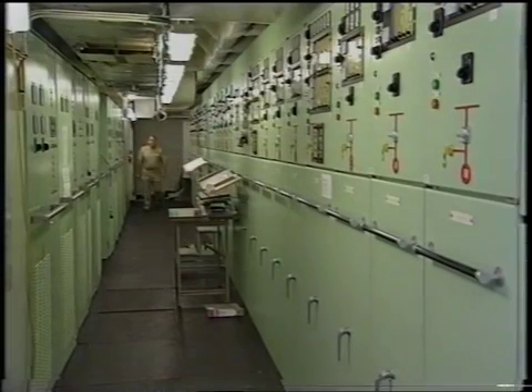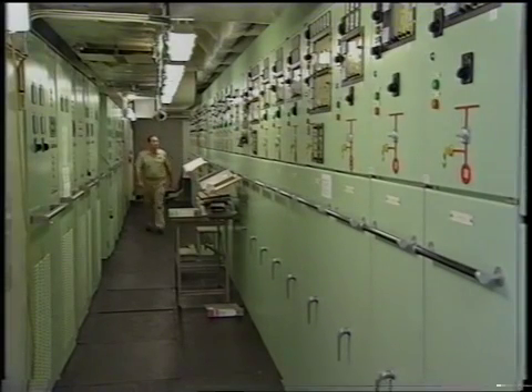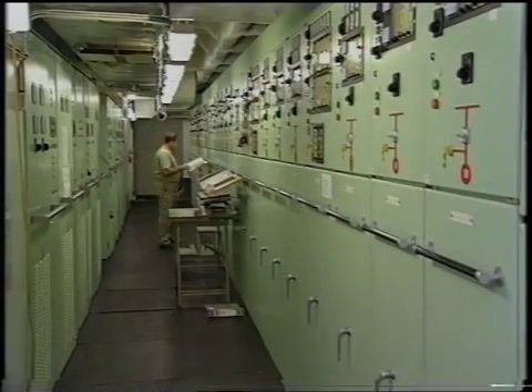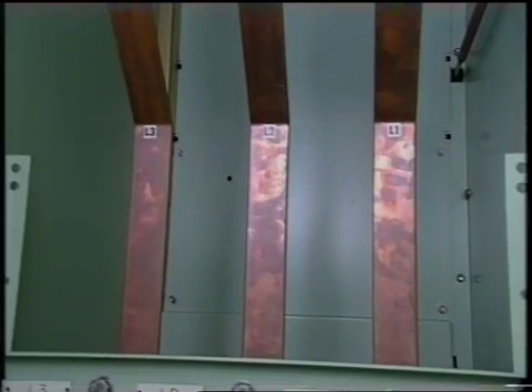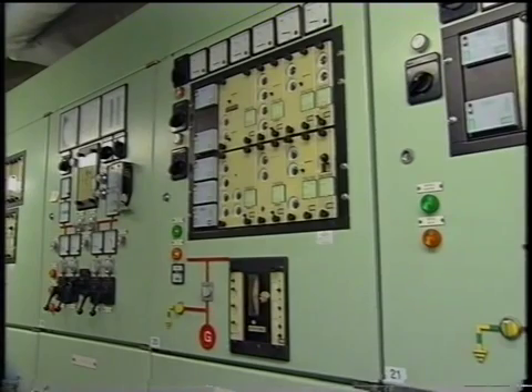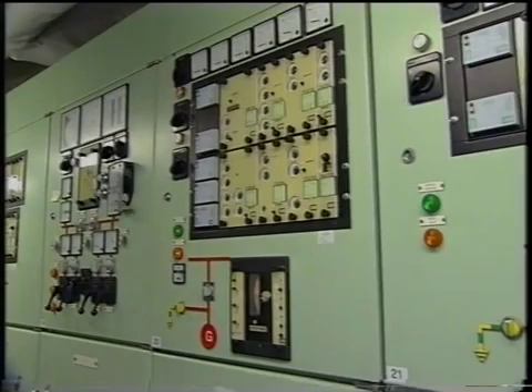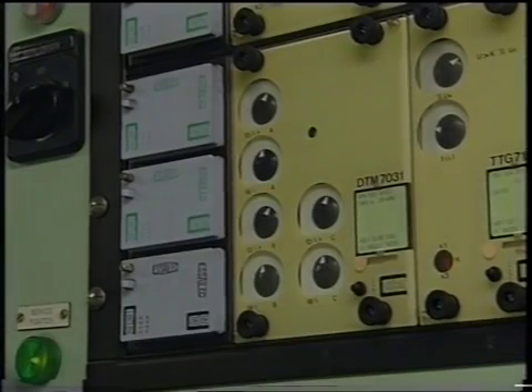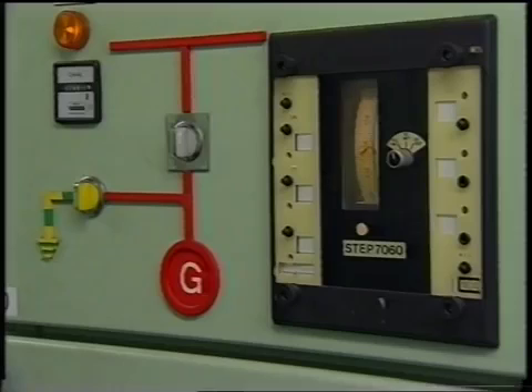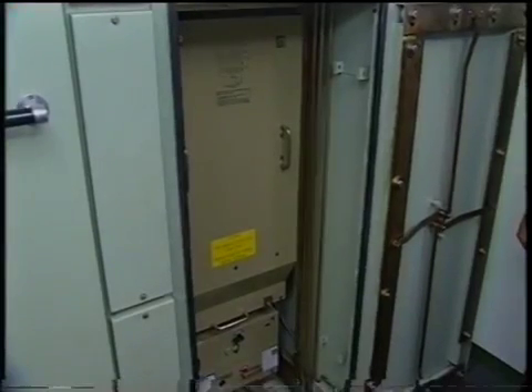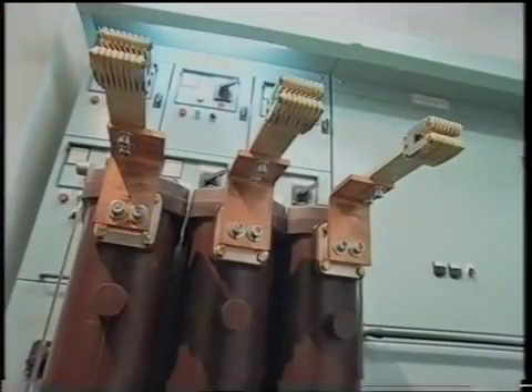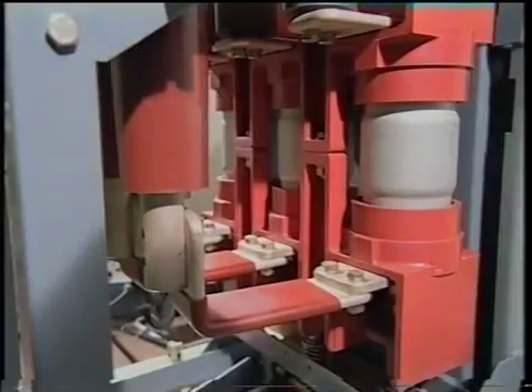The main 6.6 kV switchboard will be separate from the engine control room. Here are the 6.6 kV bus bars and the main protection relays. These protection relays continuously monitor critical operation levels such as currents, voltages, earth leakage, unbalanced loading and temperatures, and where necessary give an alarm and trip a main circuit breaker. The breakers will be of the air type or the more modern SF6 gas-filled type, or even the vacuum interrupter type.